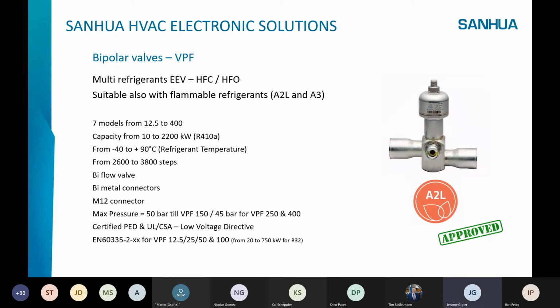We have also a bipolar valve in the catalog, called the VPF. So they are multi-refrigerant, of course. They're working for HFC, HFO, and all the flammable refrigerants, A2L and A3. They are approved for A2L. We have 7 models from 12.5 to 400. The capacity is around 10 kilowatts to 2.2 megawatts for 410A, and the temperature range is -40 to 90 degrees.